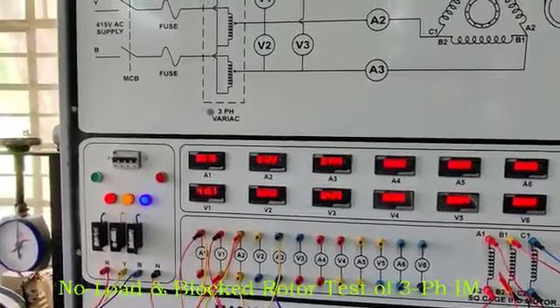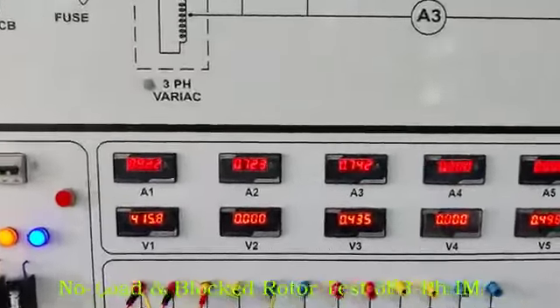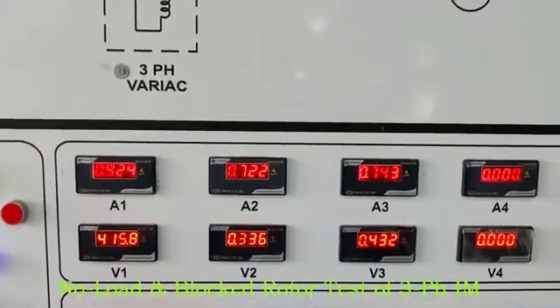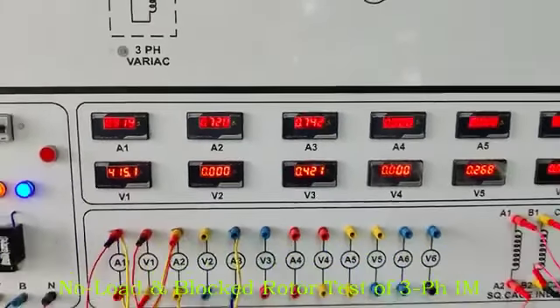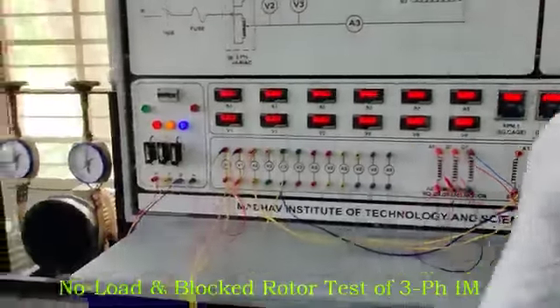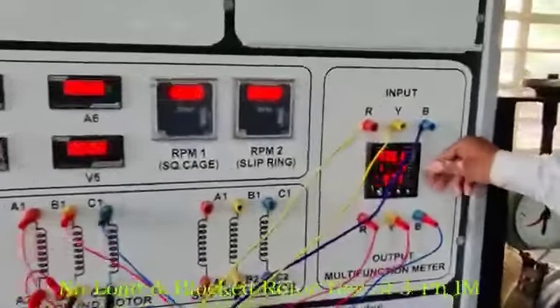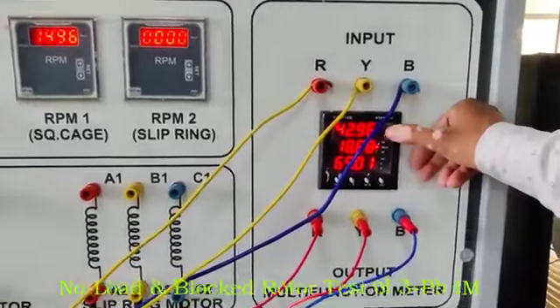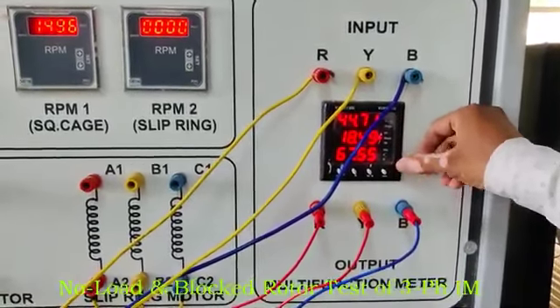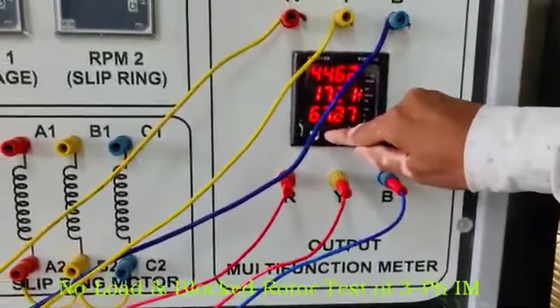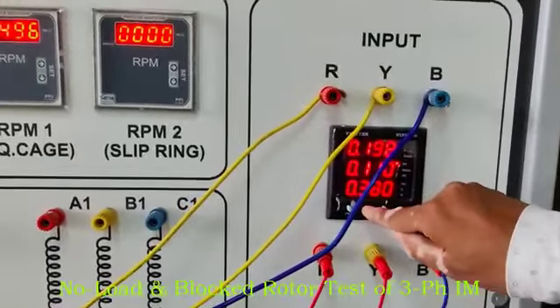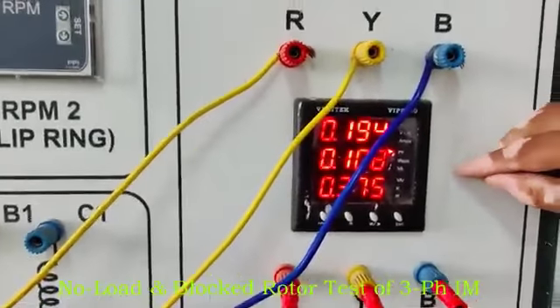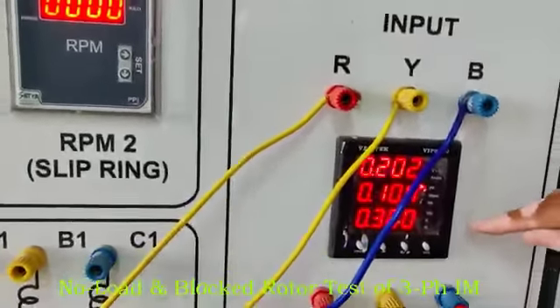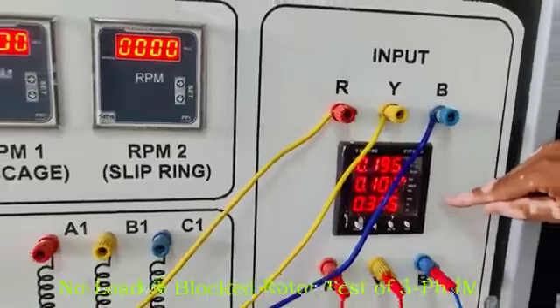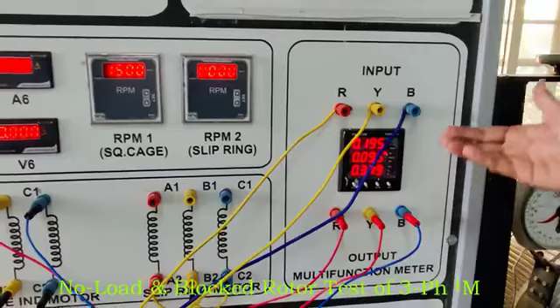At this voltage, we will take the readings 0.9, 0.7, 0.7, and this is the multifunction meter. This multifunction meter measures the wattage. There are 3 wattages, and you also have to take the power factor. The power factor with the watts is 0.19, 0.19, 0.3. So we will take the readings of power factor, power, line current, and voltage.